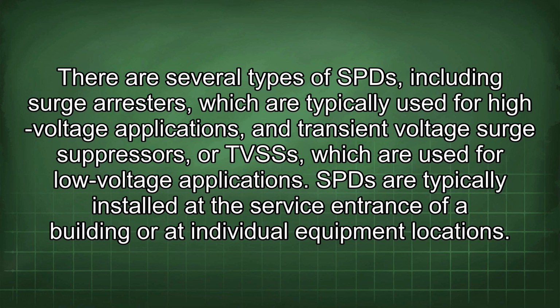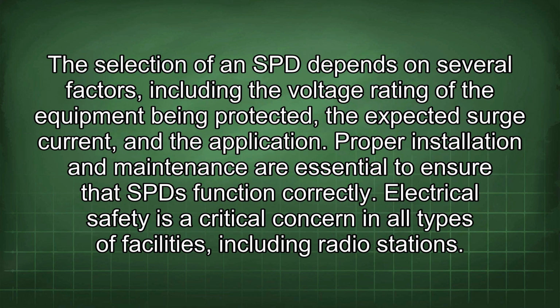SPDs are typically installed at the service entrance of a building or at individual equipment locations. The selection of an SPD depends on several factors, including the voltage rating of the equipment being protected, the expected surge current, and the application. Proper installation and maintenance are essential to ensure that SPDs function correctly.